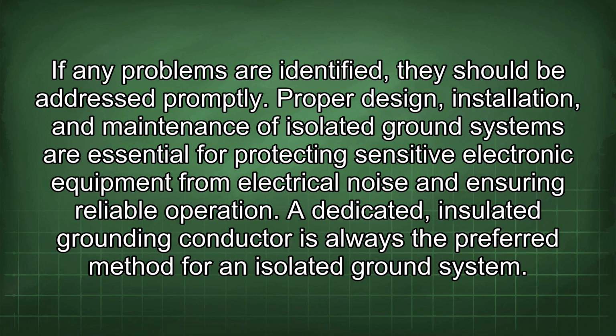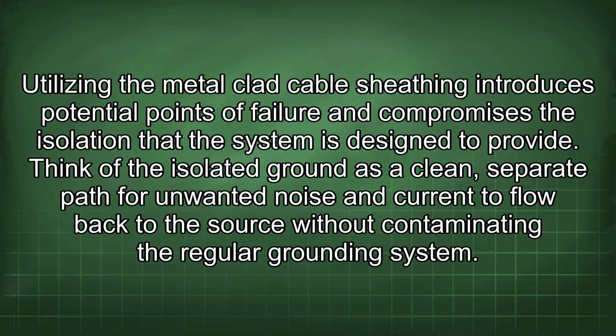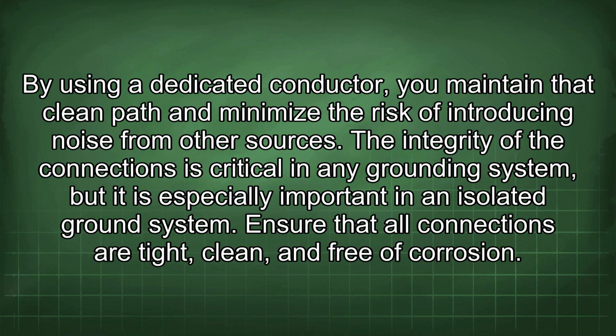ensuring reliable operation. A dedicated insulated grounding conductor is always the preferred method for an isolated ground system. Utilizing the metal-clad cable sheathing introduces potential points of failure and compromises the isolation that the system is designed to provide. Think of the isolated ground as a clean, separate path for unwanted noise and current to flow back to the source without contaminating the regular grounding system. By using a dedicated conductor, you maintain that clean path and minimize the risk of introducing noise from other sources.